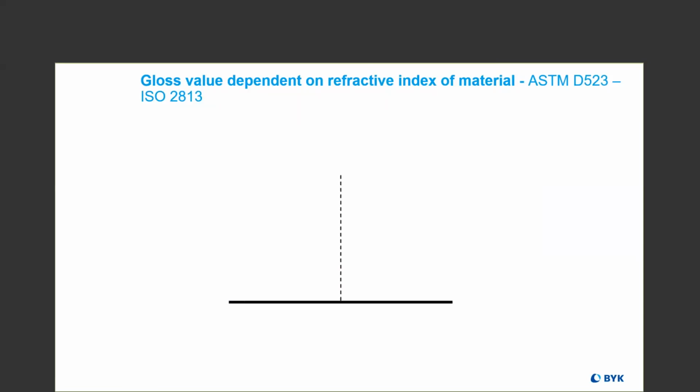Sphere instruments are going to ignore the gloss and only measure the pigmentation, so the gloss will have no effect or very little effect on the color measurements you get with a sphere instrument. So you just have to decide what's important to you and what you want to see in your color numbers.